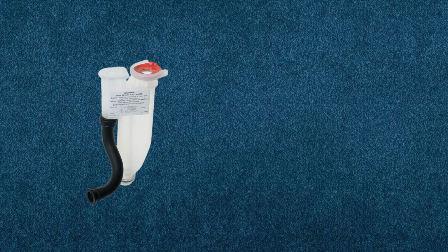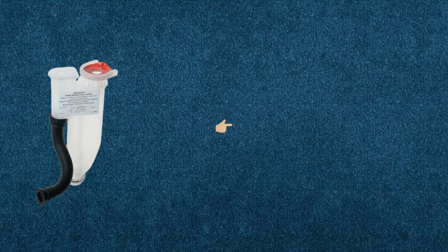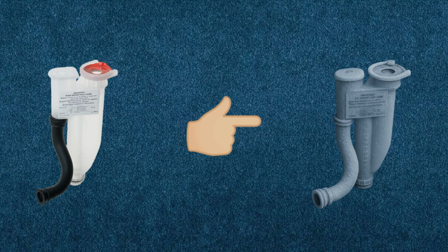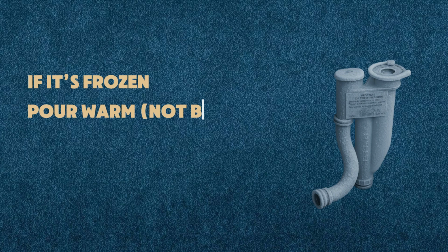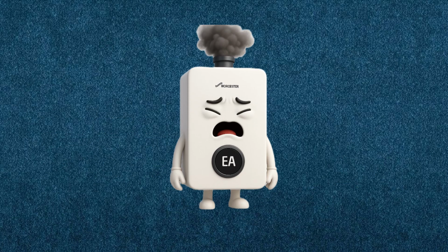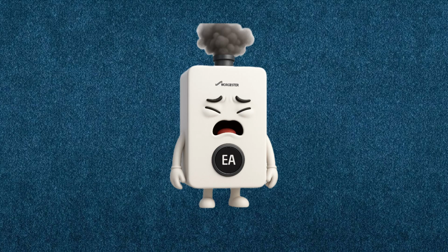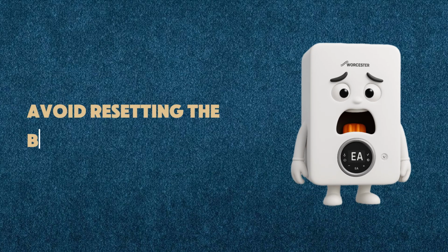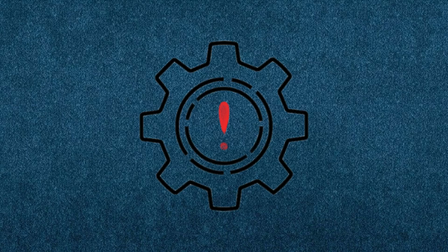3. Check your condensate pipe outside the property. In cold weather, this pipe can freeze and prevent ignition. If it's frozen, pour warm, not boiling, water over it to thaw it safely. 4. Make sure the boiler flue terminal outside isn't blocked by leaves or debris. 5. Avoid resetting the boiler repeatedly. If it keeps locking out, there's a genuine ignition fault that needs attention.